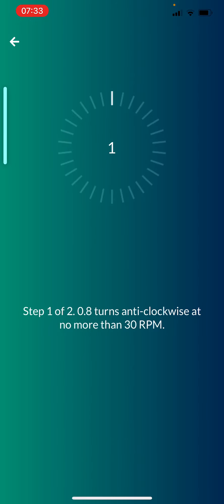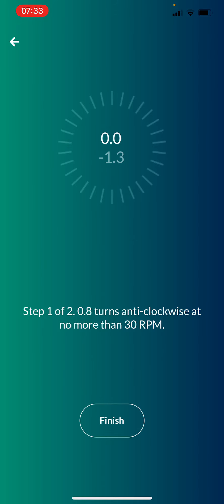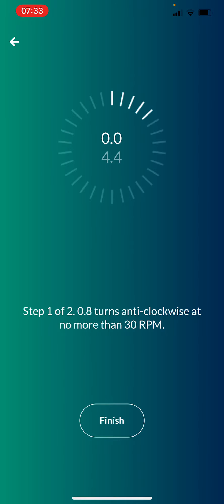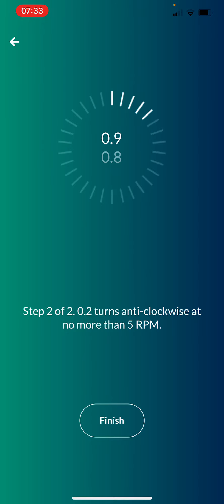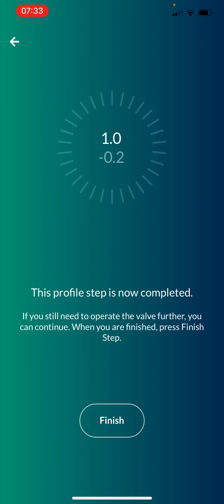The valve turn profile is now active. This example has two steps: Step 1 is 0.8 turns anti-clockwise at no more than 30 RPM — the faster part of the turn. Smart Valve counts down and says 'Start', then guides you through. If you turn in the wrong direction it gives a warning. As you approach the end of the step, it tells you to get ready to change speed. Step 2 requires a much slower rate — no more than 5 RPM — which is the critical final portion of the turn.